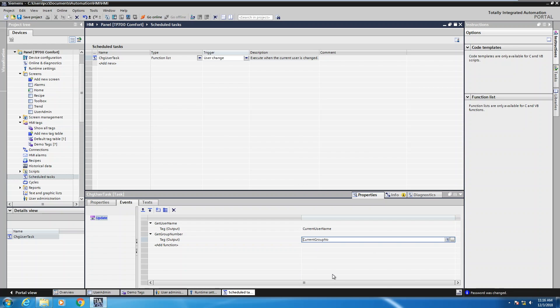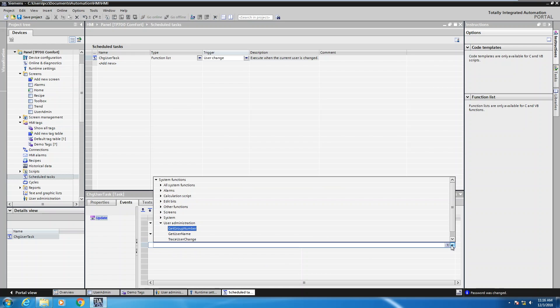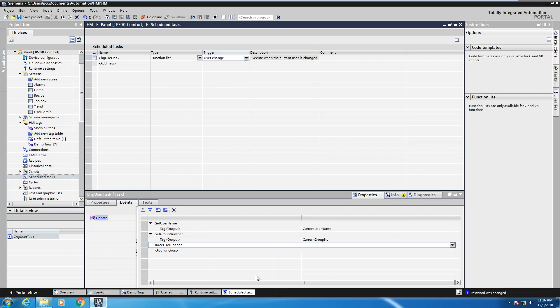When this task executes we're going to fill in the current username, the current group number, and there's one other function I'd like to add when working with user administration — it's called trace user change. All this does is it writes a system message to the alarm window that will display what's going on with the user administration when there's a user change.